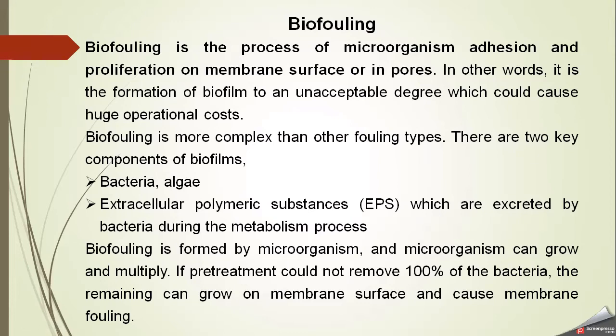There are basically two components involved in biofouling: first, bacteria, algae, or other microbiological substances; and second, extracellular polymeric substances (EPS), which are excreted by bacteria during the metabolism process. Biofouling is formed by microorganisms that can grow and multiply on the membrane surface. If pre-treatment cannot remove 100% of the bacteria, the remaining bacteria stop at the membrane, grow on its surface, and cause membrane fouling.